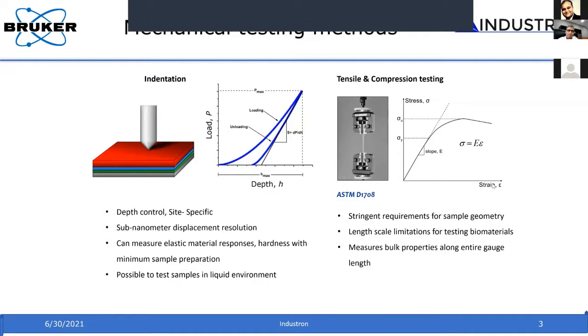When you get this load-displacement curve, you can analyze the curve. For example, the unloading curve you can analyze by measuring the stiffness. The load divided by the depth gives you the stiffness, so you fit the unloading curve and measure the stiffness. And once you have the stiffness measured, from that you can always measure the hardness and modulus by modeling.